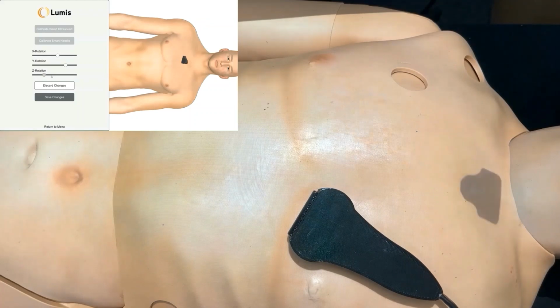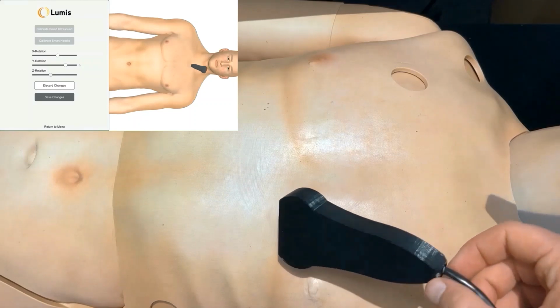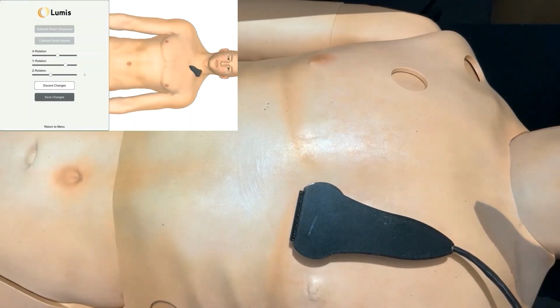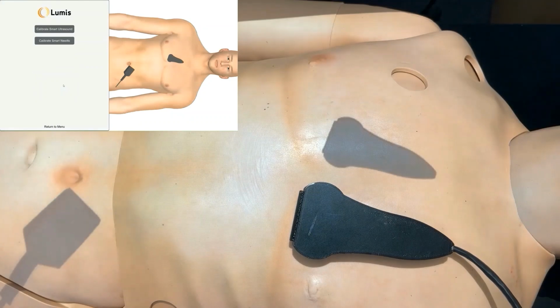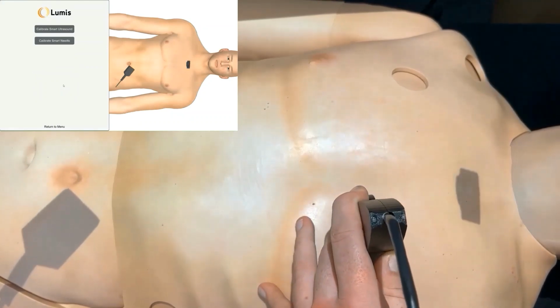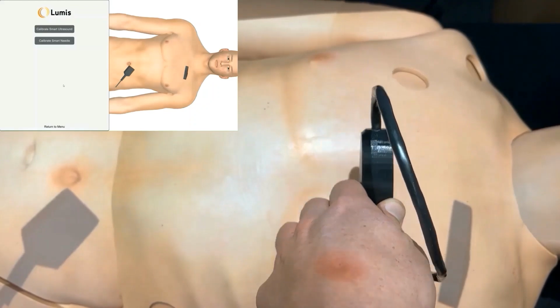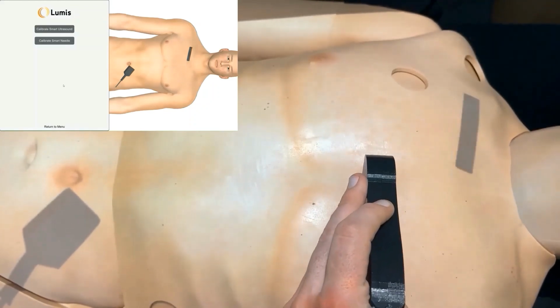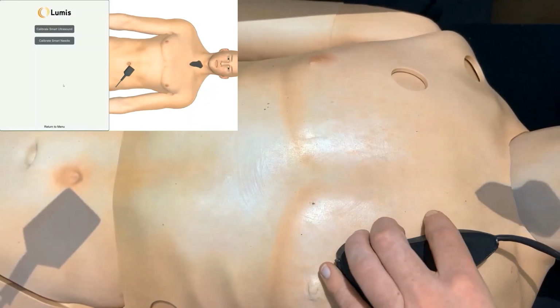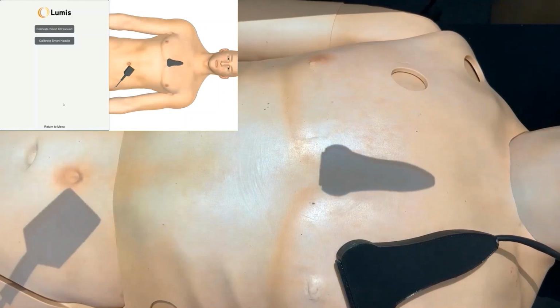As you can see here, my attempts at calibration resulted in a far poorer orientation of the virtual probe than what we had originally. You can press the Discard Changes button to revert your changes and go back to the existing calibration. That is all that is needed to set up the smart ultrasound and smart needle orientation. If you have issues tracking their position, you should check out our video on camera calibration. Otherwise, you are good to go.